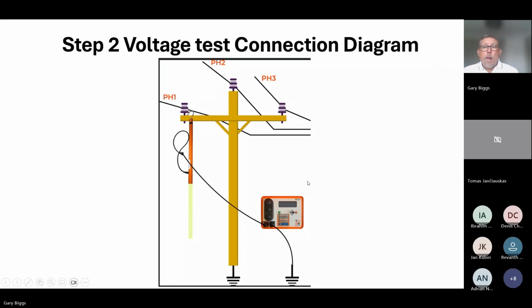So this is a little diagram showing what happens here. As I said, from the earth point of the instrument, we connect either to a known good earth if there's one nearby, or to a temporary stake that we've put in the ground. In the UK, which is where I'm most familiar with this, the stakes situation depends on the board you're working for or the area that you live in.